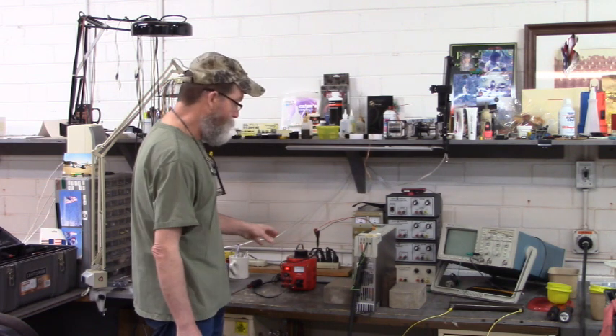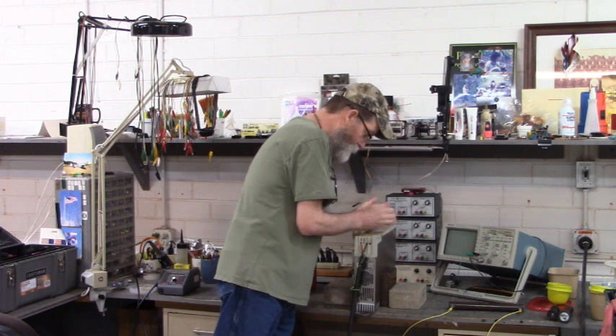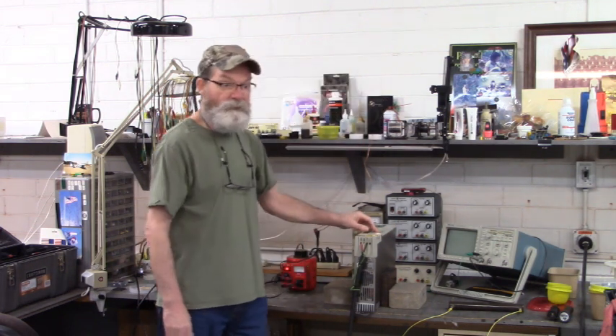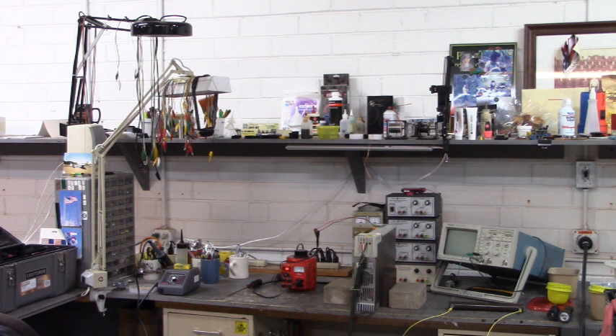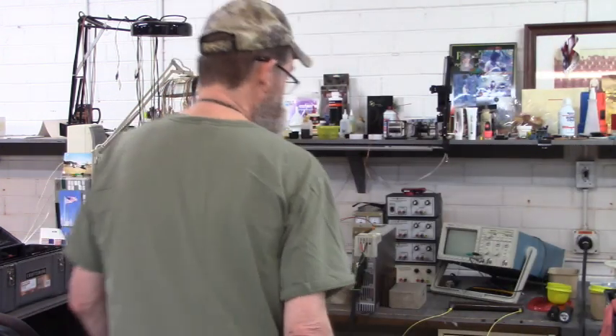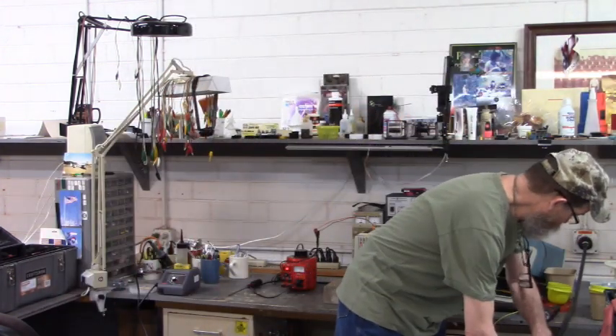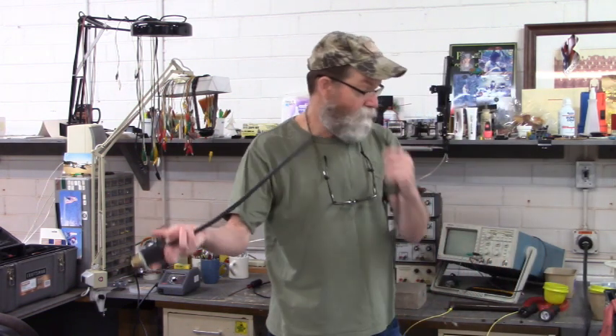Okay, we just turned on the variac and the green control power LED is on. Let's go over here and apply the 380 volts AC 3-phase to L1, L2, and L3. Did you hear the contactor energize? Did it click? I didn't hear it. Well, let's go remedy that problem. Okay, I've turned the 380 volts AC 3-phase off. Let's get unplugged from the wall just to be safe. There, we're unhooked.